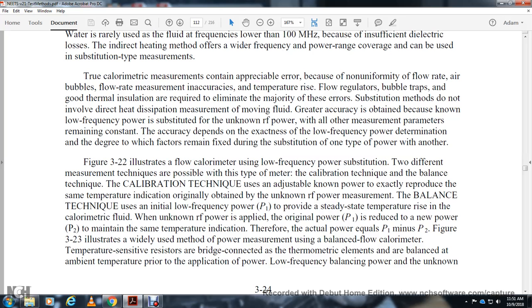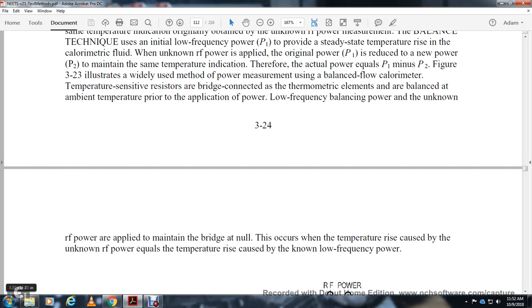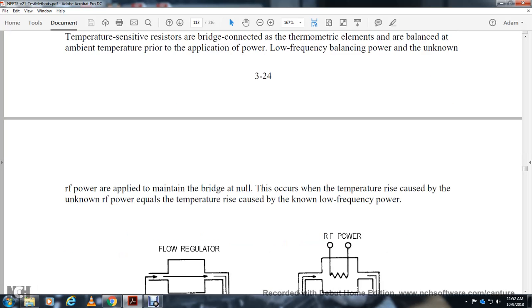The calibration technique uses an adjustable known power to exactly reproduce the same temperature indication originally obtained with the unknown radio frequency power measurement. In the balance technique, initially low frequency power provides a steady state temperature rise in the calorimeter fluid. The unknown radio frequency power is applied, but the original power is reduced to a new power to maintain the same temperature indication. Therefore, the actual power equals the original power minus the new power. Figure 3-23 illustrates the widely used method of power measurement with the balanced flow calorimeter. The temperature sensitive resistive bridge, connected with thermometric elements, is balanced at the ambient temperature prior to the application of the power. Low frequency balancing power and the unknown radio frequency power are applied to maintain the bridge at null. This occurs when the temperature rise caused by the unknown radio frequency power equals the temperature rise caused by the known low frequency power.